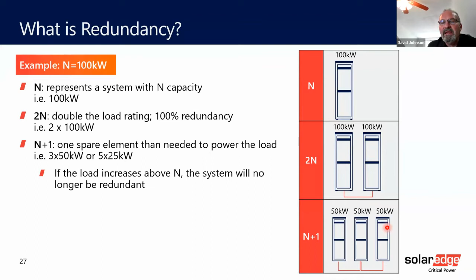In the modular approach, N plus 1, whether they're 50 kW modules or 25 kW, for 50 kW, again, our load is 100 kW. We need 2 modules to get to 100, and we have an additional 1. That's our plus 1. In a 5 by 25, we'd have 4 25s to get to the 100, and then an additional 25 kW. So that's basically what redundancy is. And again, the reason we need it nowadays is the move of society to the digital age, and everything we do is digitally based. There is more need for redundancy and uptime.